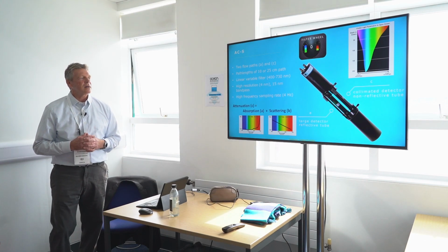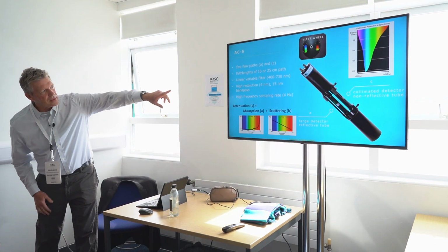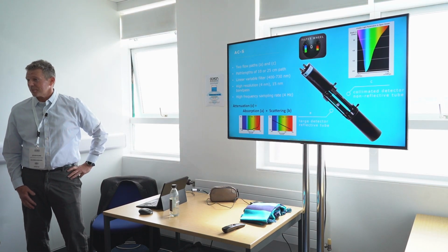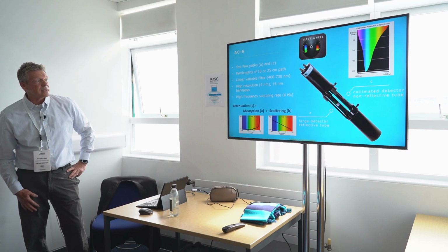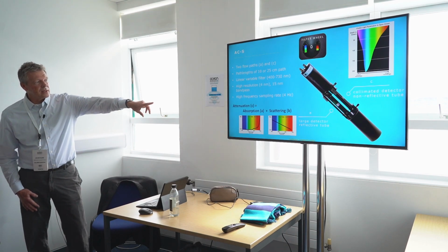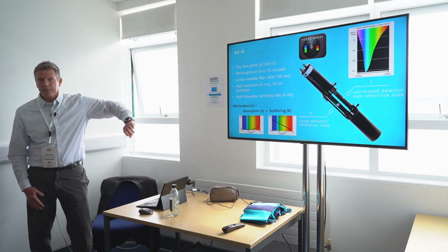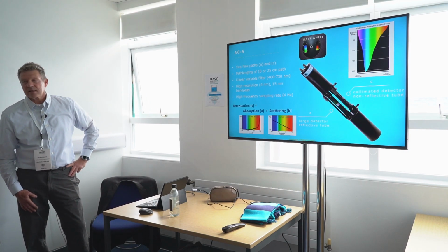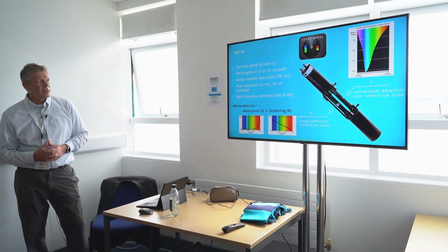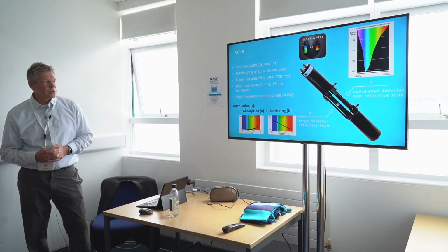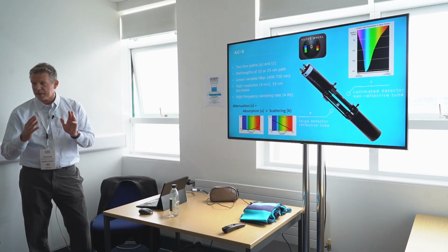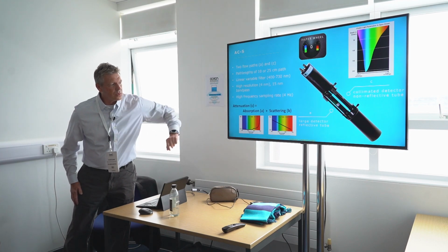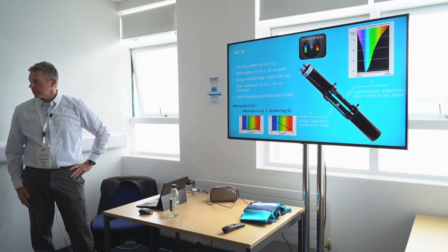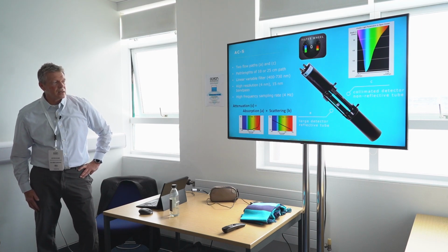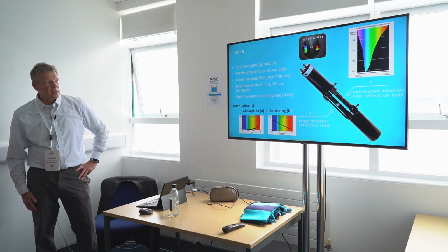The ACS is a flow-through system, shown here on the right. It has 2 flow paths, the A and the C component. A is for absorption and C is for attenuation. Light entering the ocean is absorbed differently depending on the wavelength. The highest absorption is in the red side of the spectrum, and on the left side, blue is the least absorbed. That's why ocean water is blue. On top of that, we have the highest scattering in the blue region, but the lowest scattering in the red part of the spectrum. That adds to the fact that the ocean is blue.